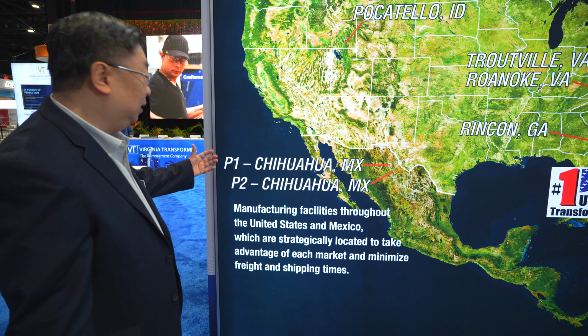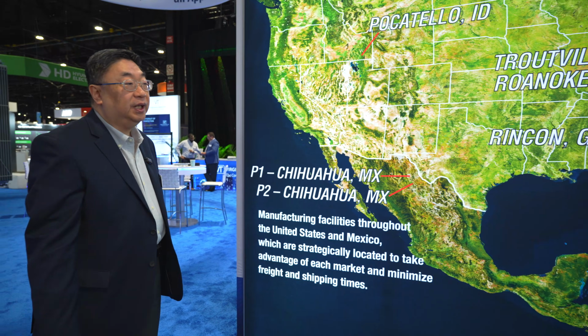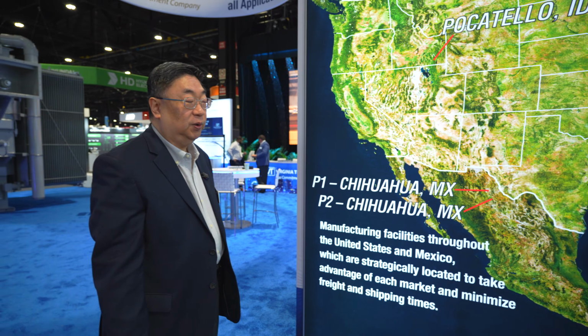Mostly what they do is make what we call distribution transformers, so that's basically below 69 kV. Those are pole mount transformers, substation transformers, and dry type transformers, all made in P1 and P2. But P2 also manufactures what we call medium power transformers. So we categorize power transformers - the definition of a power transformer is any transformer that is 69 kV and above from a primary voltage side.